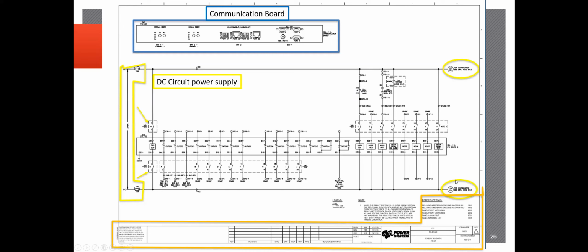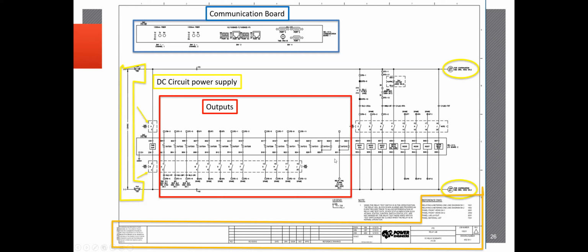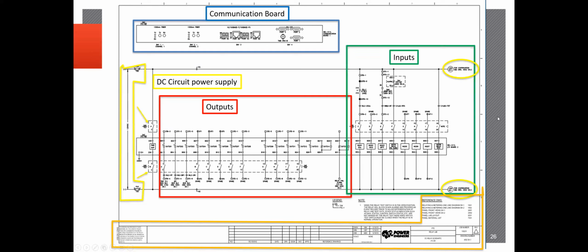Associated drawings that may go on to other sheets, because a lot of times these relays have so much going on with them that they can't fit them all on one print. Your output contacts, identifying those, it's usually pretty clear because they label them, but verifying that each contact is supposed to be normally open or normally closed, depending on what the circuit is involved with and how it's supposed to function. Verifying your inputs, anything that may be coming into the relay that would primarily be important, such as output contacts, trip contacts from the breakers, other stuff like that. Any notes that may be associated with it.